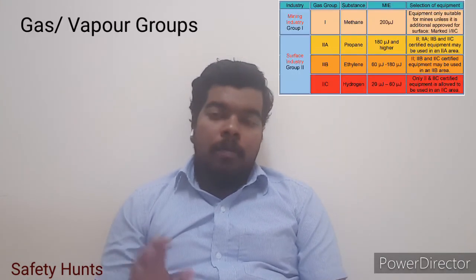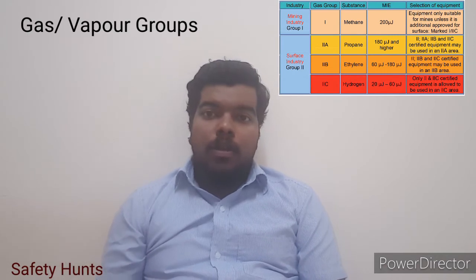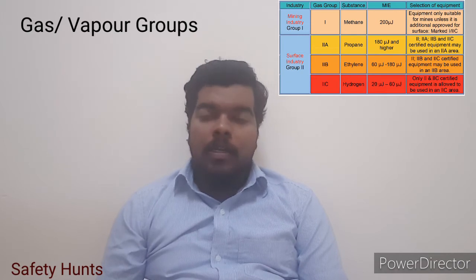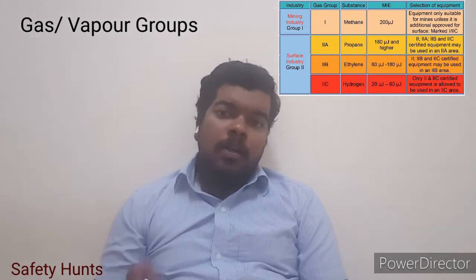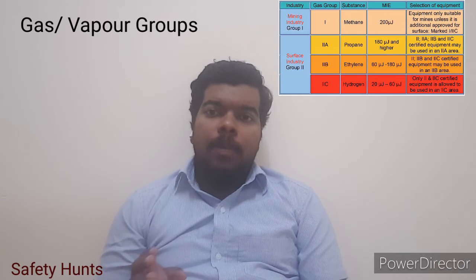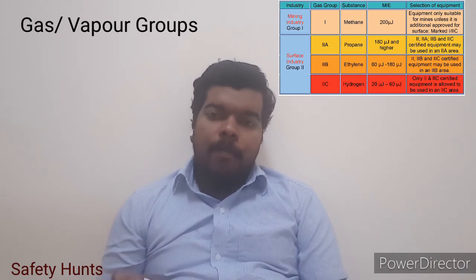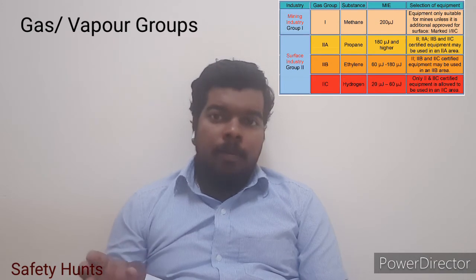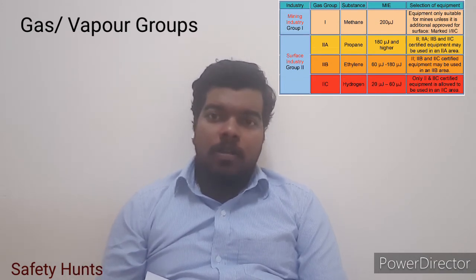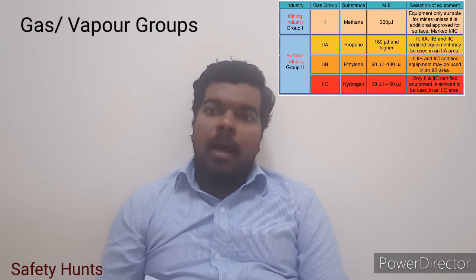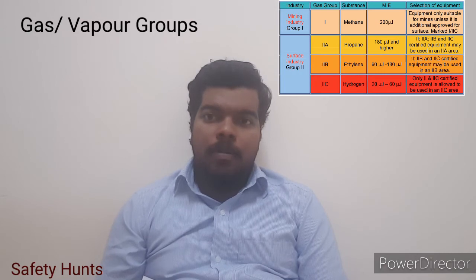Let's see the gas and vapour groups. Gas and vapour groups are further divided into three categories: 2A, 2B, and 2C. Under 2A, the gases like methane, ethane, and propane are included. Under 2B, gases like H2S — which is hydrogen sulfide — and ethylene are included. And 2C includes hydrogen and acetylene as the best examples.